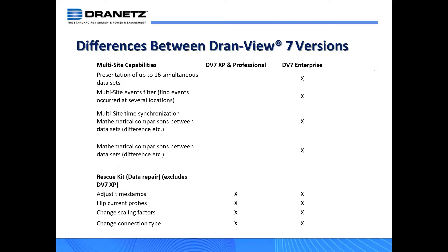All versions of Dran-View, with the exception of Dran-View XP, have what's called the rescue kit. That's for situations where you forgot to set the time, set the wrong time zone, or forgot to set it at all — you can adjust and slide the time around. Maybe you forgot to put in the current probe scale factors correctly, forgot you were connecting to a CT, or accidentally had the CT arrow pointed in the wrong direction. These things can be corrected within the rescue kit.